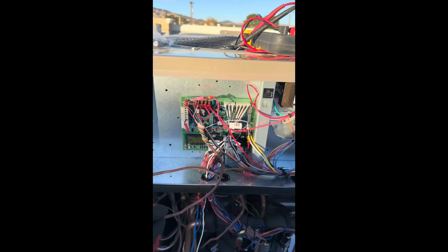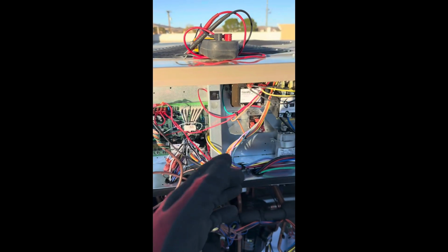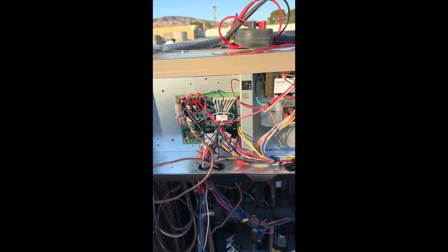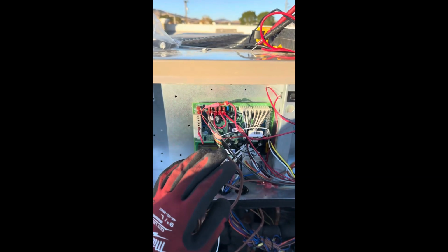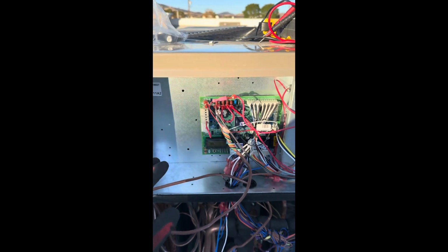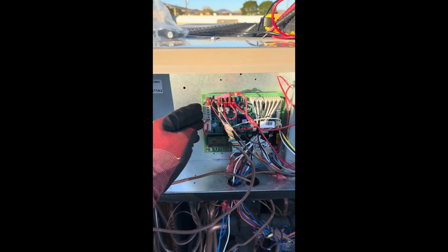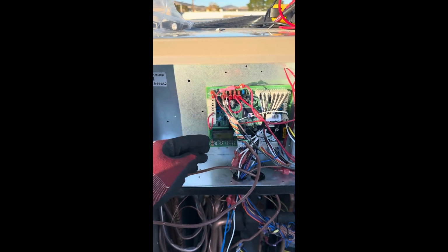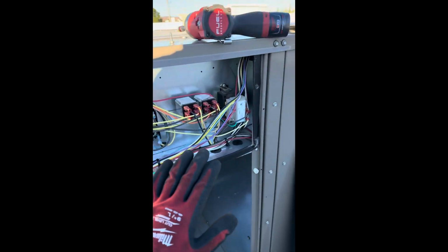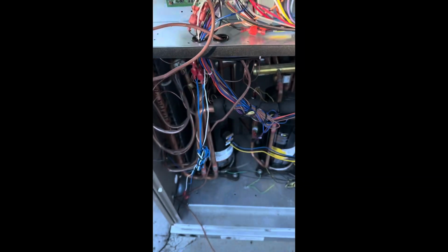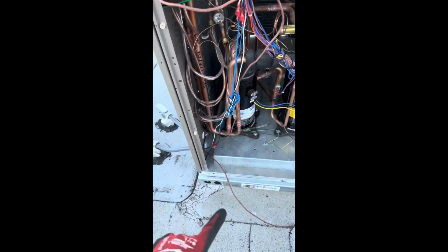So to figure this out, I wanted to isolate it, whether it was on the low voltage side or within the actual equipment. So what we did basically was reset the transformer after shutting off the power, and we isolated the low voltage and turned the unit back on. No tripping of the transformer whatsoever. So what that tells me is we have our short here in the actual low voltage.